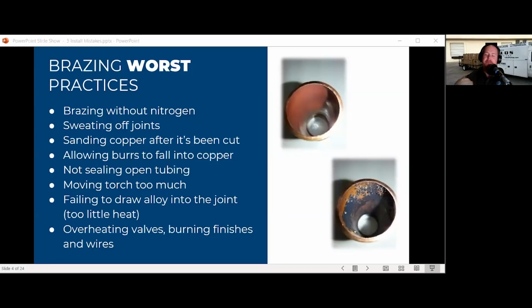So many times the nerdy technician types focus on things like evacuation and airflow testing and all that, but then miss the fundamentals, like making sure that your copper stays sealed, even when you're working with tubing. If you're out in the field and you're installing a compressor or an evaporator coil, when you're in between steps, use a little bit of painter's tape even, just to block off the ends and reduce the amount of moisture and air getting in there. Painter's tape isn't going to be completely sealed, but it's a temporary measure while you're working. Just keep the open tubing sealed as best you can.